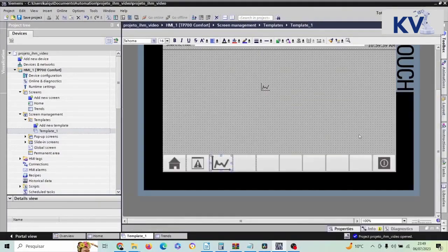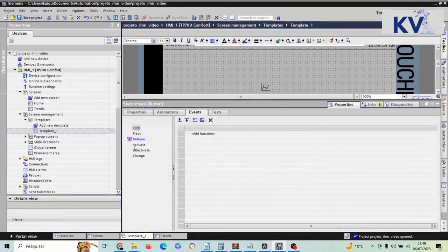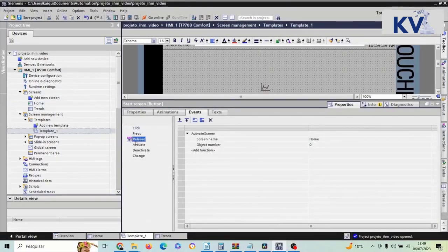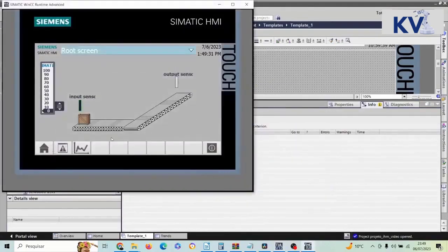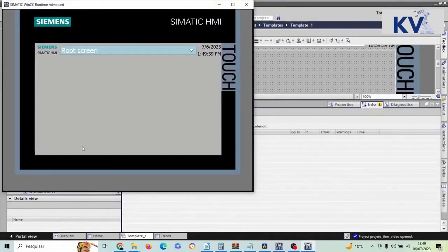The home screen comes in by default on the release event — so when I release the button, it will go back to the home screen. Let's test it to see if it works. I'm on the home screen; if I press my trend button, I go to the trends screen. But look at the problem it generated: my icon menu is only appearing on the home screen, so we have to make that menu appear on all screens.